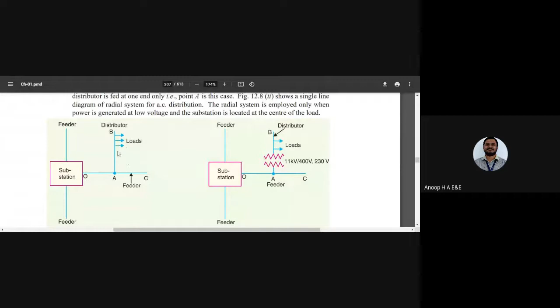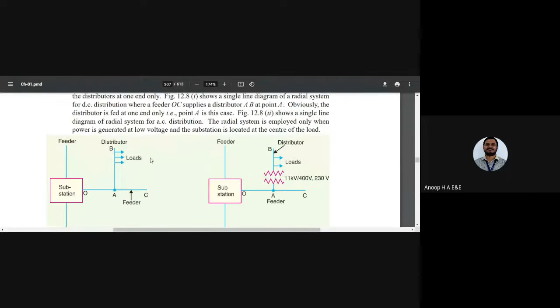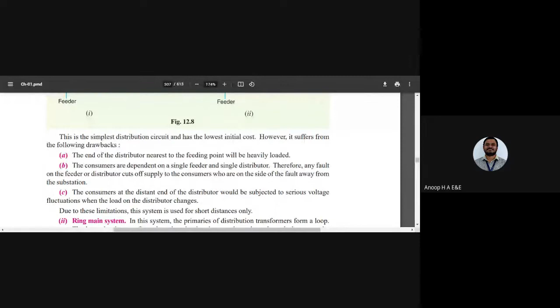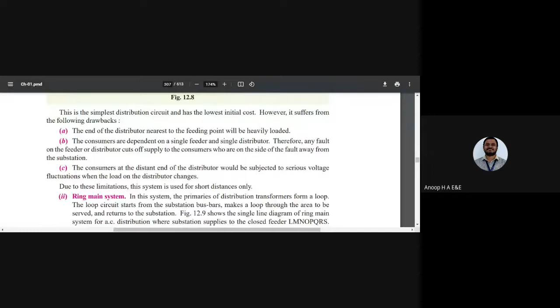So radial system, you have to remember that. Directly the loads are connected, in case of industrial loads, from the feeder, and next you have the use of a transformer on the other part. Any fault on the system would generally cause serious problems on the load side, so the loads will not be able to run. Therefore any fault cuts off the supply to the consumers. The consumers at the distant end would have serious voltage fluctuations if there are sudden load changes on the distributor side, because it is directly connected to the feeder.